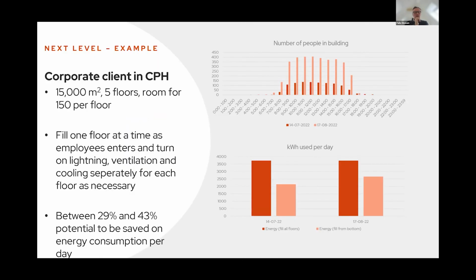So what if we took a more radical approach, using knowledge of seasonality, the day of the week, and how people generally come to the office? The top graph shows two different days—one in mid-July, typical vacation season in Denmark, and one in mid-August when everyone is back from vacation. The turnout on those two days was quite different. People start showing up in the morning, mostly between 8 and 9 o'clock, then gradually leave around 4 or 5 in the afternoon. But the turnout on these two days is extremely different, and on neither day are we anywhere close to actually filling the building with people.